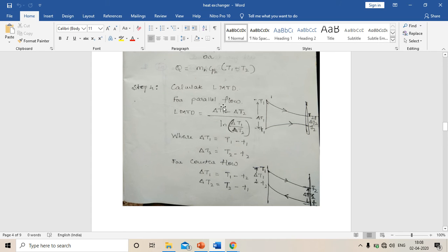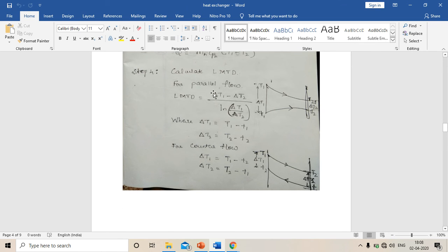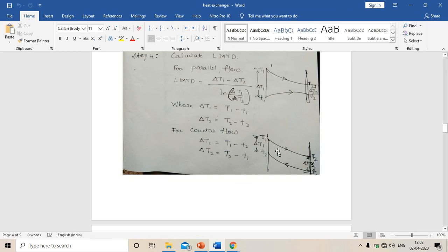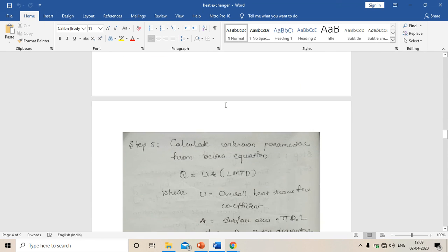Step four: calculate LMTD. The LMTD equation is the same for both parallel and counter flow heat exchangers: LMTD equals (delta T1 minus delta T2) divided by ln(delta T1 / delta T2). However, delta T1 and delta T2 change depending on whether it is parallel or counter flow. For parallel flow: delta T1 equals T1 minus t1, and delta T2 equals T2 minus t2. For counter flow: delta T1 equals T1 minus t2, and delta T2 equals T2 minus t1. This is the key difference between parallel flow and counter flow heat exchangers.